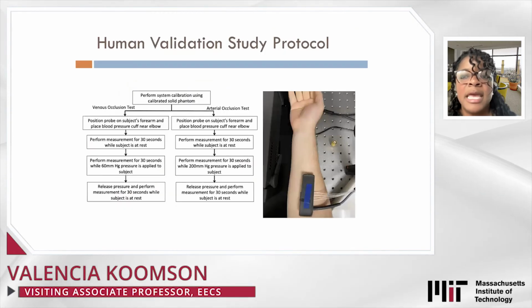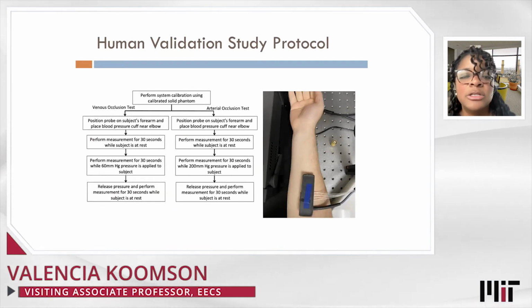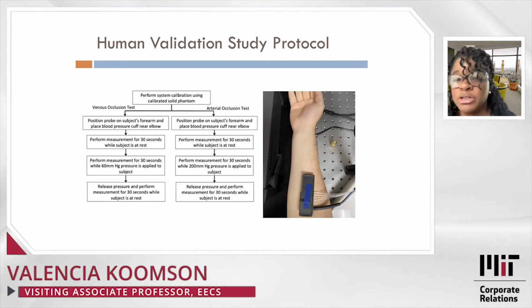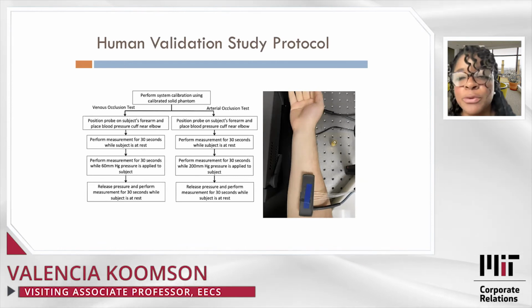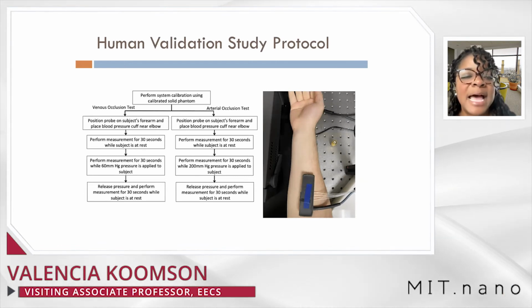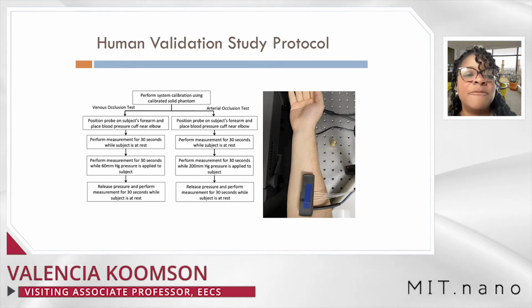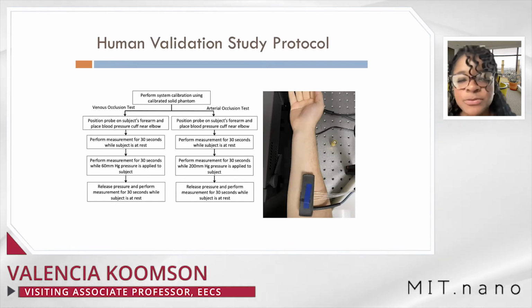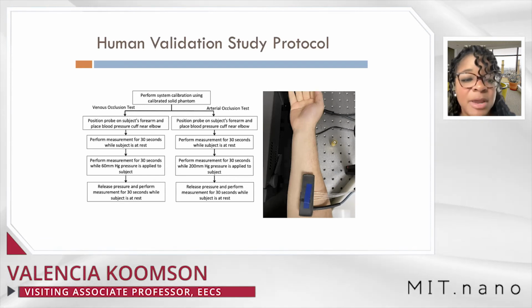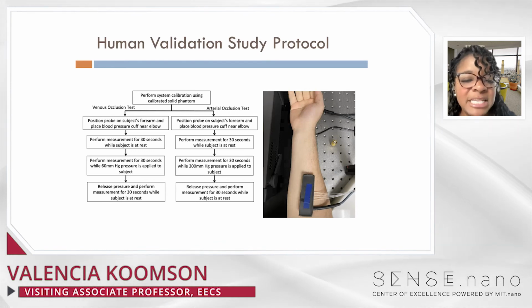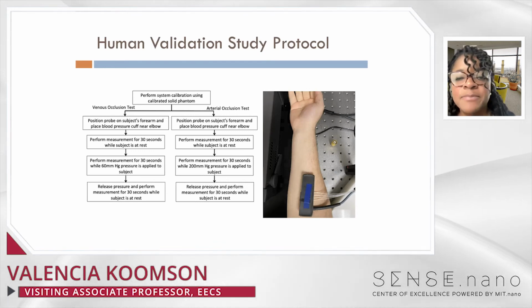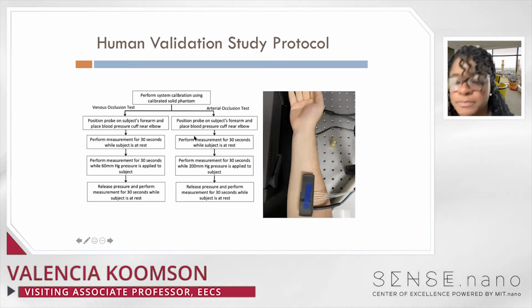Here is our human validation study protocol. We have two different tests that we're seeking to do to validate the system: a venous occlusion test and an arterial occlusion test. We place the sensor probe onto the forearm and apply a blood pressure cuff near the elbow. For venous occlusion, we have the subjects at rest for 30 seconds, and then we apply a 60 millimeter mercury pressure, and then we release that pressure and perform measurement for 30 seconds. For arterial occlusion, we apply much higher pressure in order to block both arterial and venous flow.